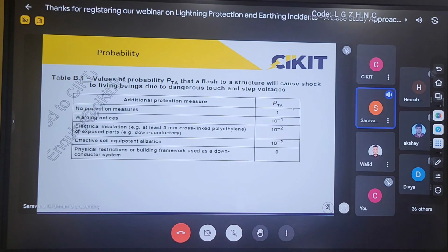So the next step is electrical insulation. By providing PVC insulation or any other insulation, I can avoid direct contact. If I provide insulation, the risk can be reduced by almost 100 times. The third one is equipotential bonding, and physical restrictions. By providing obstacles that avoid contact, the value of PTA can even be reduced to 0. These are the parameters related to reducing damage to human beings from step and touch voltages. Apart from this, the conductor we use is always buried at a depth of around 500 mm, which also helps reduce damage due to step and touch voltages. That is the reason we always recommend burying the conductors of the lightning protection system below 500 mm. So if a discharge happens, it won't have much impact on human beings.